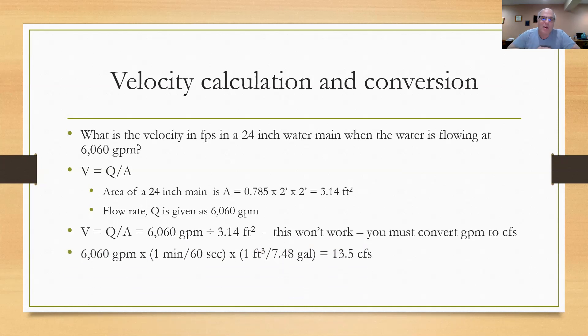What I chose to do is convert the gallons per minute to cubic feet per second. I took 6060 gallons per minute multiplied by one minute over 60 seconds, and one cubic foot over 7.48 gallons, which comes out to 13.5 cubic feet per second. Now I can take V equals Q over A and take 13.5 cubic feet per second divided by 3.14 square feet. Cubic feet in the numerator, square feet in the denominator cancel out, leaving only feet per second, and I come up with 4.3 feet per second.